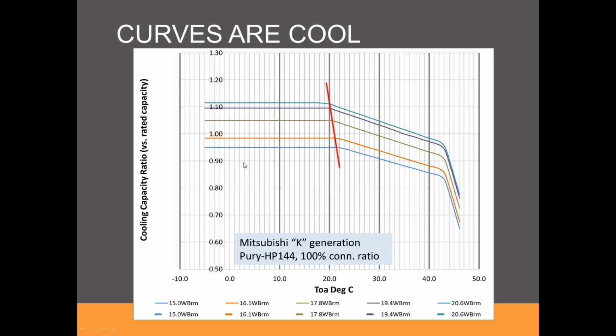And you can see that the key difference between this curve and a typical curve is that there's a distinct change between what we'll call the low condition shape of the curve and the high condition shape of the curve. And by the way, there's a boundary condition that is at a different point depending on what the indoor wet bulb condition is. So there's really three different curves represented here, one for the low condition, one for the high condition, and a third to represent where that changeover or that segmentation or inflection occurs. As already mentioned, this sort of shape for the curve applies for cooling capacity, heating capacity, cooling power, heating power, and so there's three curves associated with each of those four.